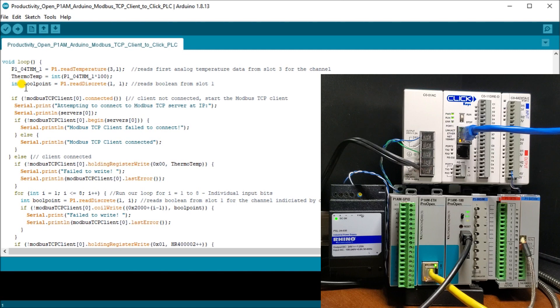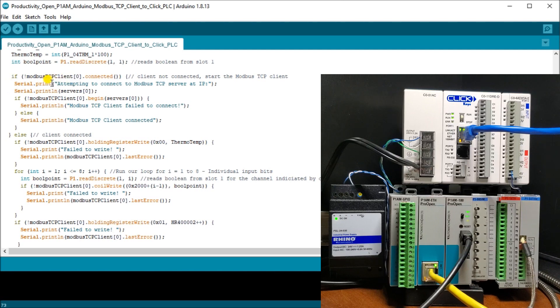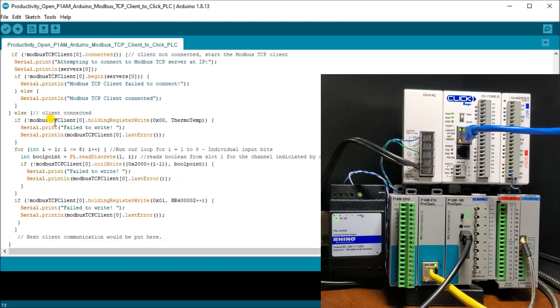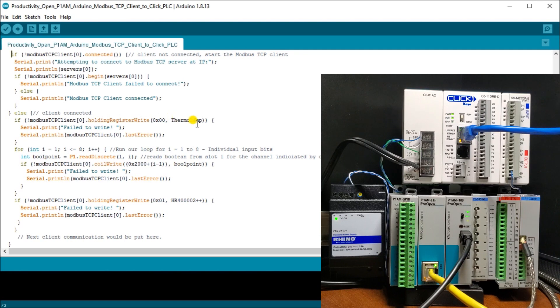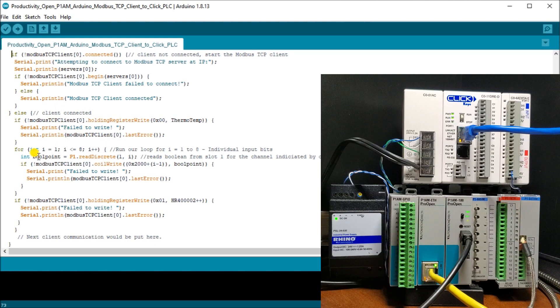Then what we do is we're going to use the boolean points to read the boolean points in our program. So next what we do is we're going to ensure that we have a connection to our client and the first client zero. And if it's not connected, then what we do is we say that we failed connect. If it is connected, when we say connected, then once we have connection, then what we do is we will actually take our holding register, write value and write to zero, which is the first register, DS1 in the Click and write a thermal temperature into that register. And if it fails, then it'll come up with our serial print and it tells us look it failed.